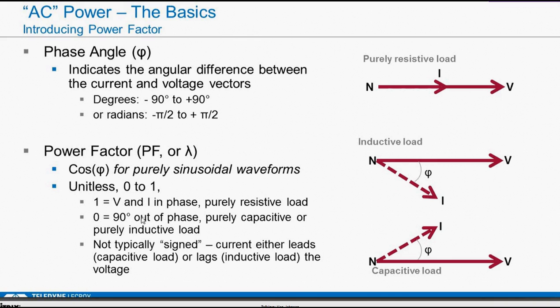Power factor is how we usually think about this. It's the cosine of the phase angle. It's unitless, and it's always positive. There's never a negative one power factor. It's always 0 to 1. And then you have to know whether it's leading or lagging. In our case, where the voltage is rotating counterclockwise, when the current is leading, that's what happens on a capacitive load. Or in this case, it's lagging. When these rotate counterclockwise, therefore, it's an inductive load.